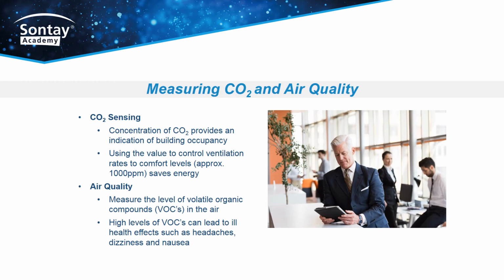Measuring CO2 and air quality. CO2 sensing. The concentration of CO2 provides an indication of building occupancy. Using the value to control ventilation rates to comfort levels, approximately 1000 ppm, saves energy. Air quality. It measures the level of volatile organic compounds, VOCs, in the air. High levels of VOCs can lead to ill health effects such as headaches, dizziness and nausea. Good quality air is another factor affecting the well-being of building occupants.